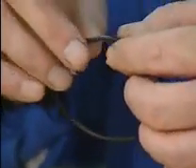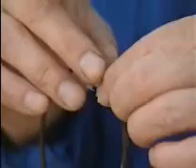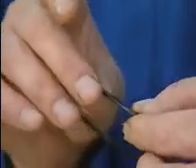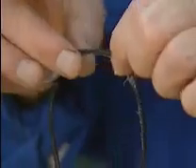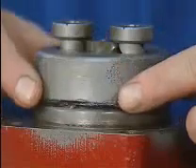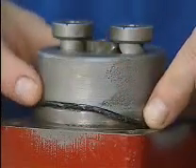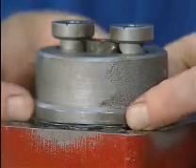The lubricant that's used must be compatible with the fluid in the system and with the material that the O-ring is made of. If the wrong lubricant is used, the O-ring could react with the lubricant and the O-ring could be damaged. Next, the mechanic places the O-ring onto the sleeve on the flange. The lubricated O-ring should fit easily but snugly into position, with just enough room to allow for compression.